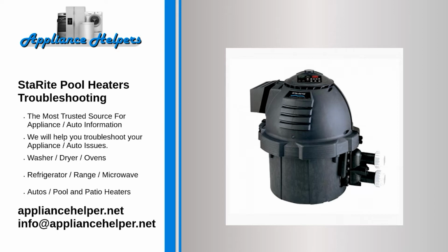If your heat pump is on, but not running, make sure all valves are in the correct position to allow proper water flow. Also, ensure that the filter and pump basket is clear of debris. Also, remember that the filter pump needs to be running before the heat pump can operate.